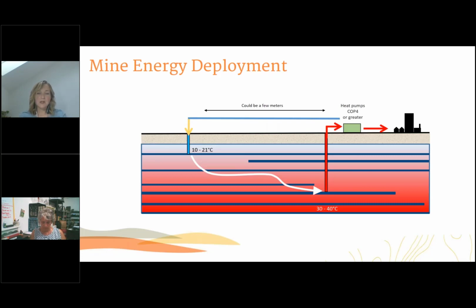And we normally look at removing 4 to 5 degrees of temperature from the ambient mine water temperature. So if you're looking at getting a megawatt from a mine, you're looking at a flow rate of about 50 litres per second. We're also looking at whether we can take more than 4 or 5 degrees out. Could we increase that a bit if we've got a big flow path, so that you could have a lower flow rate and your wells would cost a bit less? So we're doing some sensitivity analysis around all of that.